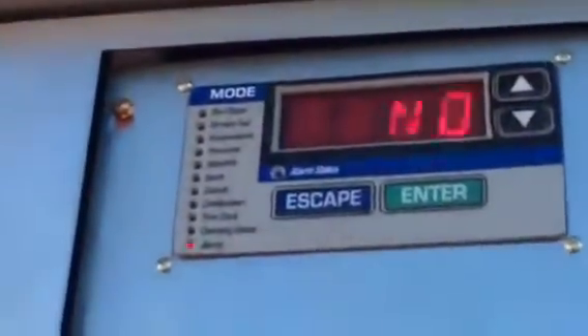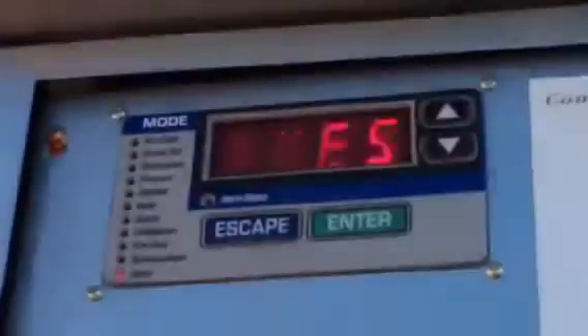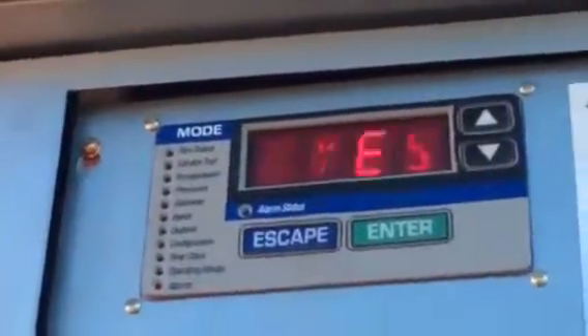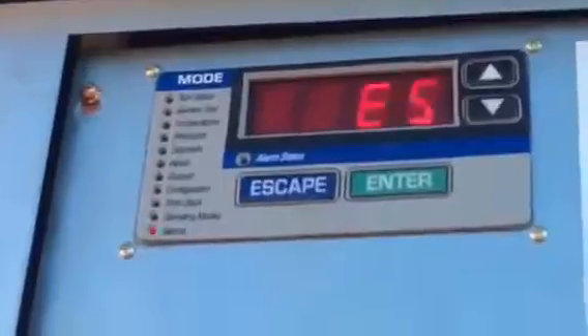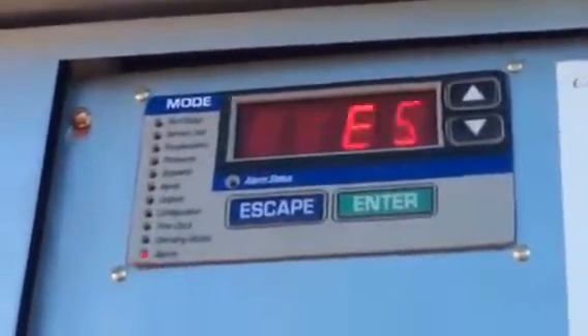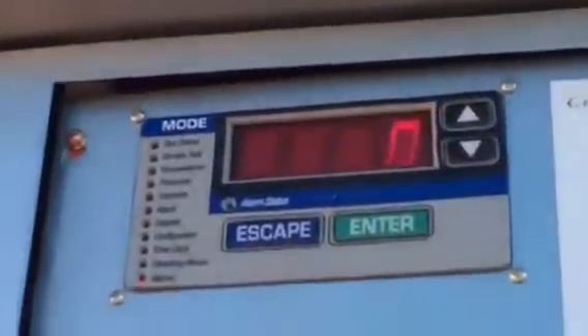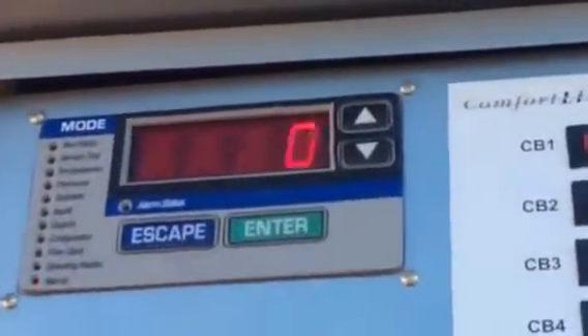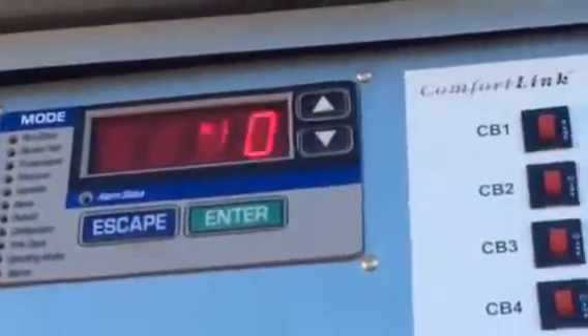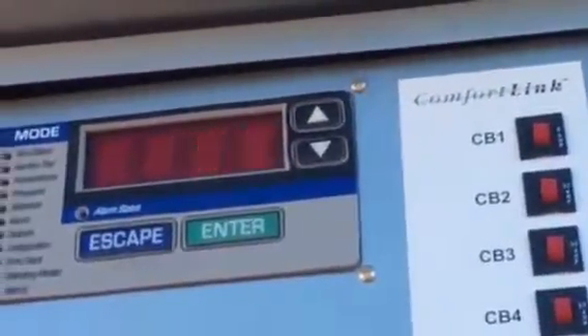So I entered the password and now no is flashing. I'm going to turn it to yes, hit the up arrow, because now that it's flashing I can change it. I always have to hit enter before that value to make it flash so I can change it. I'll hit yes, and that would have reset any current alarms it had. Of course, there were no current alarms, so effectively did nothing.